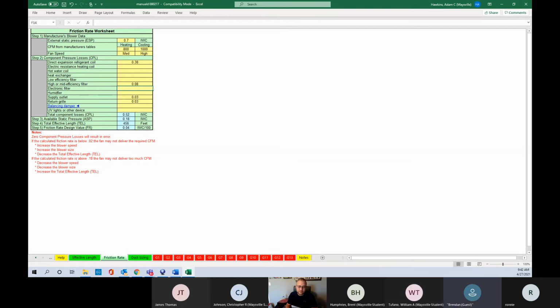Now they've changed everything, right? Then you throw a little dirt on the coil. Then you throw a little dirt in the ductwork. Then they go into their bedroom and they close some of their vents off because this one blows too hard, or they put a rug over that one or whatever, right? Any changes to that system are going to cause more issues. But from a design standpoint, from the beginning, you're already undersized.